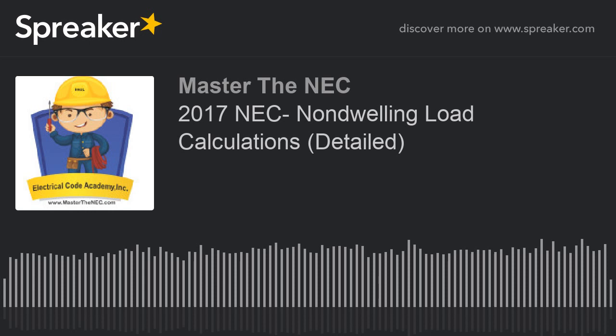So I've already done the general use, I've done the fixed multi-outlet assemblies, and now I have these two receptacle values. Remembering, they're not considered continuous load at this point. They're just general use receptacles. The next thing the code tells me is that in a normal commercial application, I've got receptacles, and I get to apply a demand factor to this.